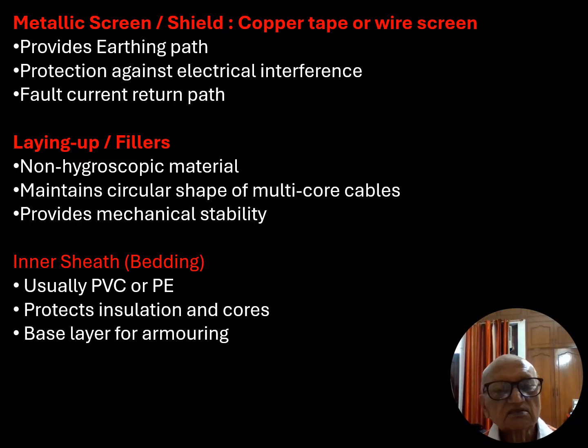Friends, the armored cable is also provided with metallic screen or shield. It is copper tape or wire screen. It provides earthing path, protection against electrical interference. It provides fault current return path.